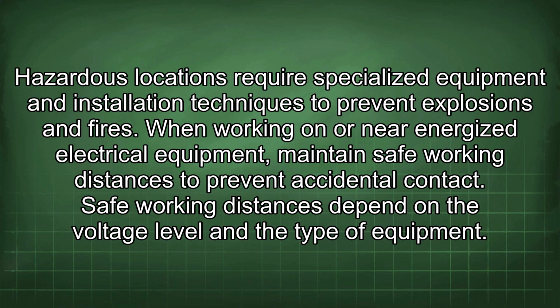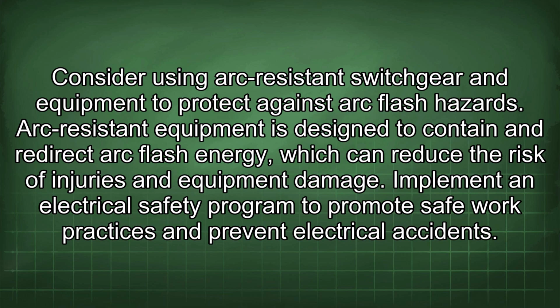When working on or near energized electrical equipment, maintain safe working distances to prevent accidental contact. Safe working distances depend on the voltage level and the type of equipment. Consider using arc-resistant switchgear and equipment to protect against arc flash hazards.